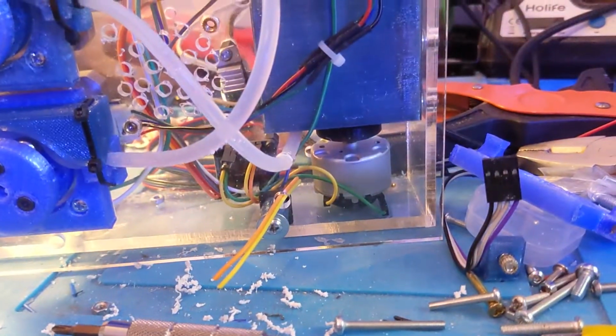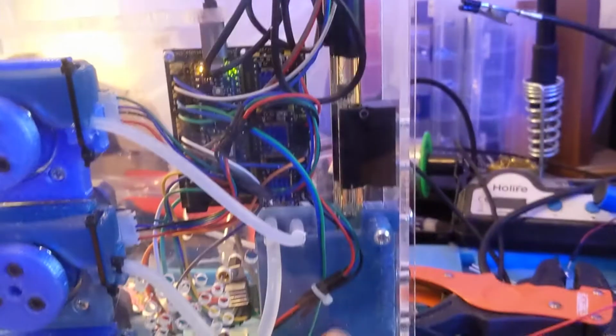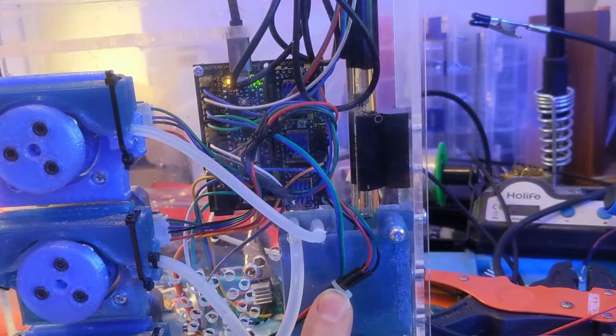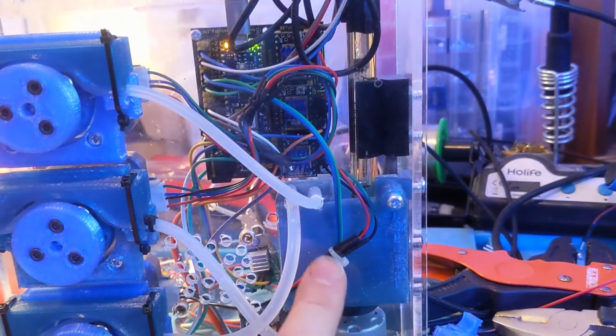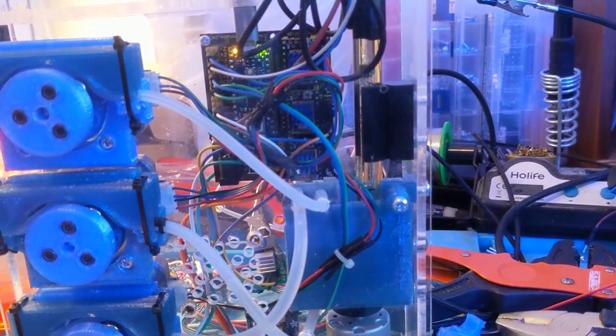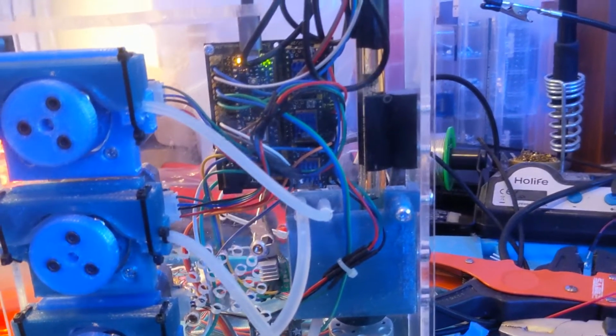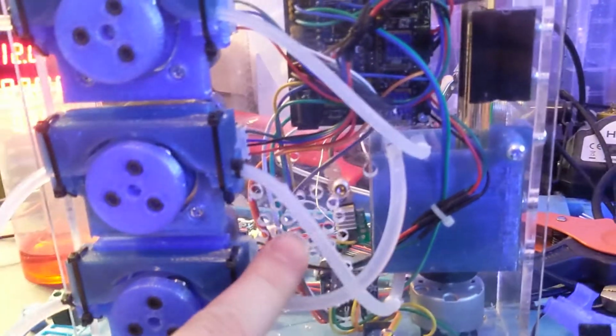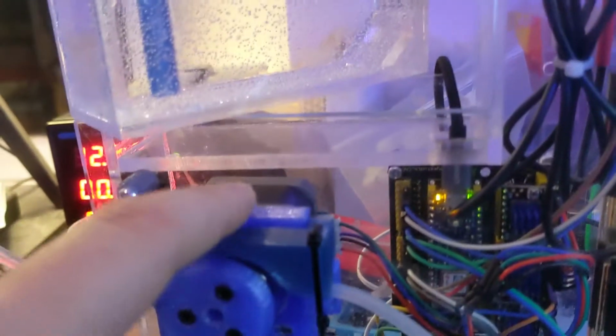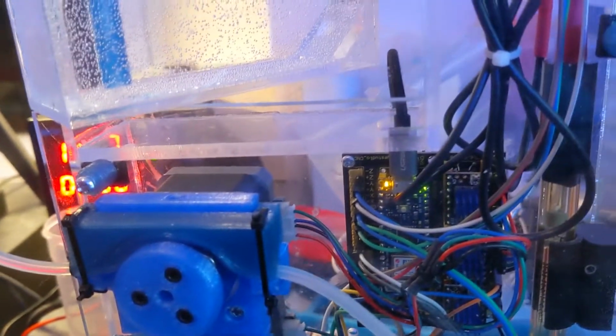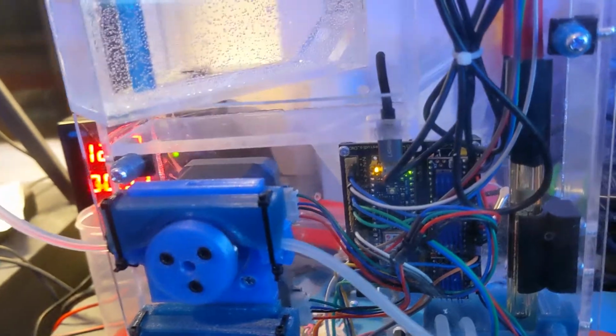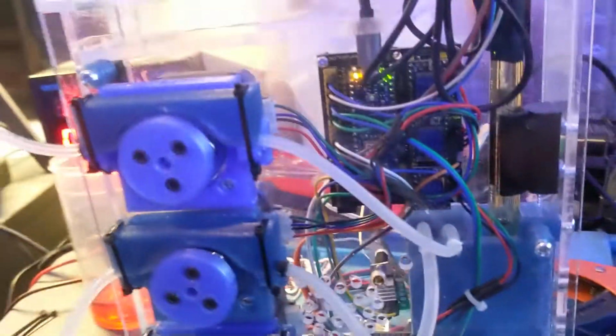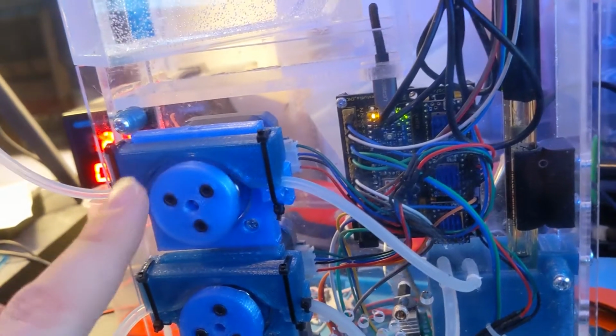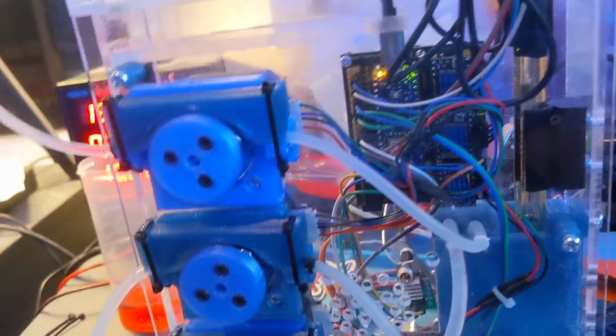So it's just done a bit of a stir using those magnets. It'll be taking another couple of pH readings to begin, just to make sure that it has a reliable starting point. And then you'll see it start to dose. If you're wondering, by the way, what these randomly drilled holes in the front here are, the stepper motors that run these titration pumps are incredibly accurate. They're much more accurate than normal peristaltic pumps, which is why this does not need any sort of sensor counting the drops that go in there, because this pump can actually dose reagent at 0.1 milliliter accuracy.